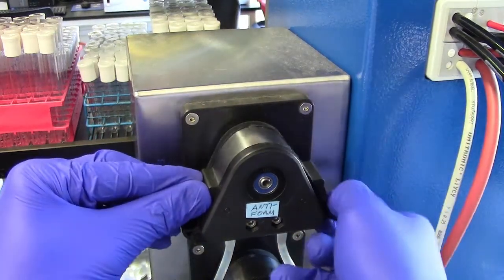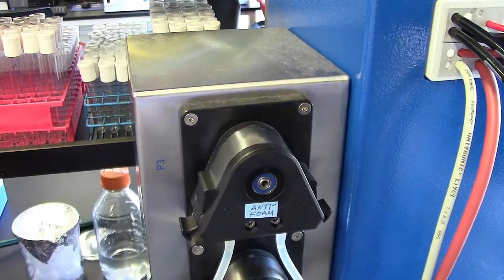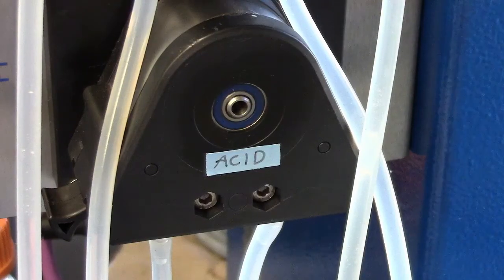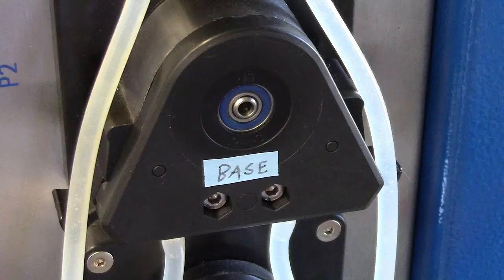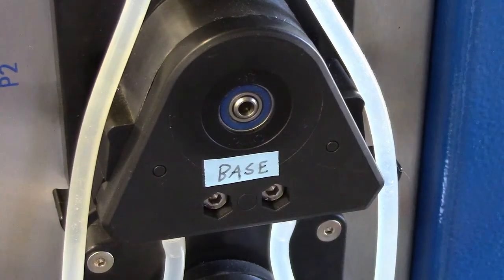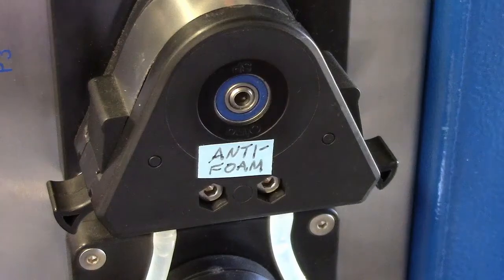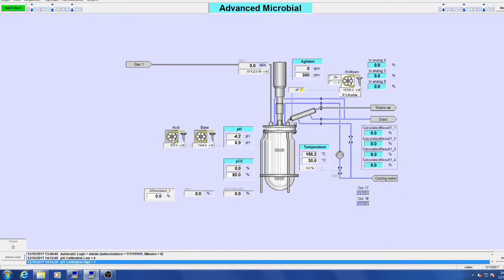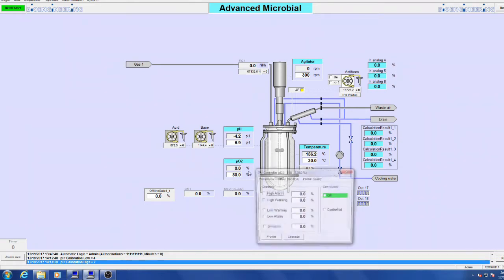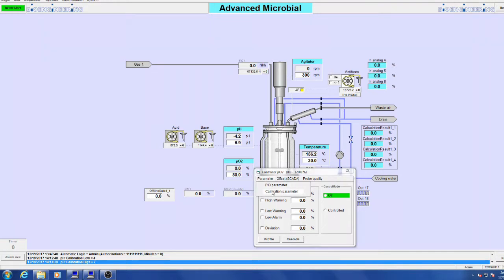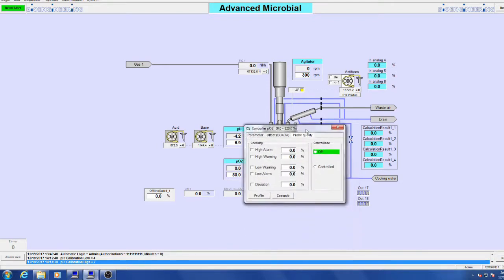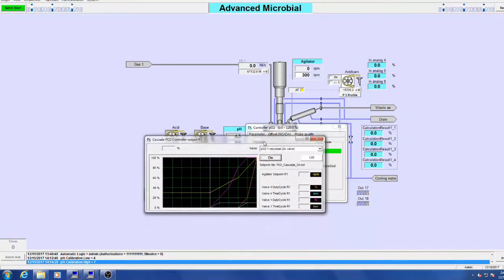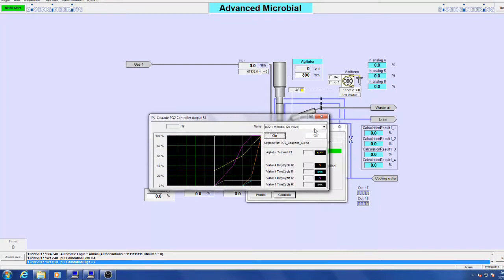These pumps are controlled by the operating software and are labeled according to their default designation in the operating software. On our machine, 2 pumps feed in acid and base to regulate the pH of the culture media, and the third feeds in anti-foaming agent should it be required. These can be configured to run automatically in the operating software using measurements obtained by the pH probe and the anti-foam probe. But don't let these designations limit you. Clever use of the addition pumps can allow for flexible fermentations, and they are the easiest way to add inoculum or media that cannot be autoclaved. We'll talk more about this in a later video.